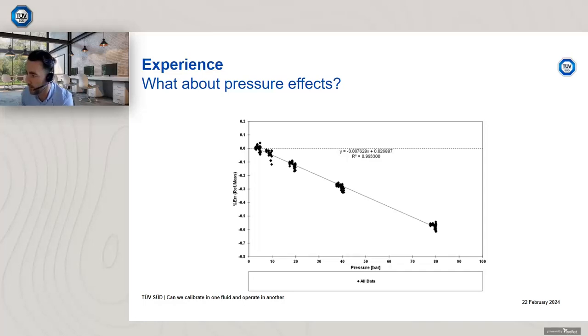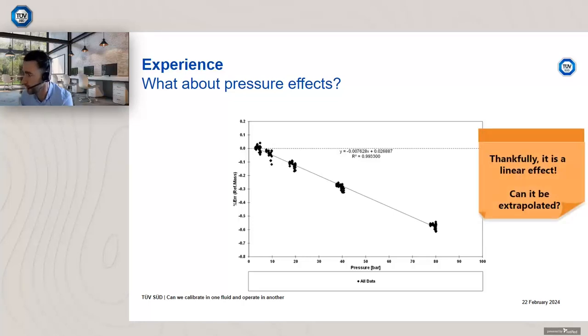You can see we have the pressure effect there, that first term, so the gradient ultimately from the curve, or from the fit. Then we also have an offset, which is ultimately what the meter could have been adjusted by. So the meter was slightly out of specification by approximately 0.027%, and this could be adjusted. And then we have that zero effect, that pressure effect, which is minus 0.0076% per bar. So it's a linear effect. That's very good, but can it be extrapolated?